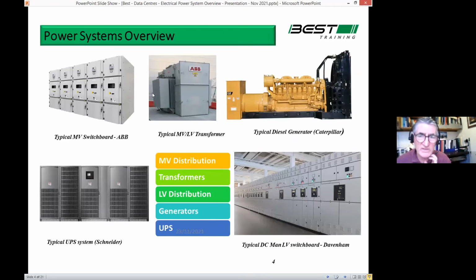Right, and the main components in the power system that we'll be looking at there. So medium voltage switchgear, that's what it looks like. You can see there on the top left-hand image, there's 5 cubicles, we call them. And each of those cubicles is a circuit breaker. So they're the equivalent of the little trip switch in your house, an MCB, or the trip switch, some people call it. So that's what each of those are. But obviously, they're handling vast amounts of power. So it's much more complex, much bigger, etc. And then the transformers, which convert the power from high voltage down to lower voltage. That's what we're seeing there. And we'll be looking at that.